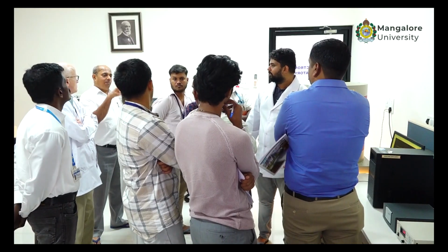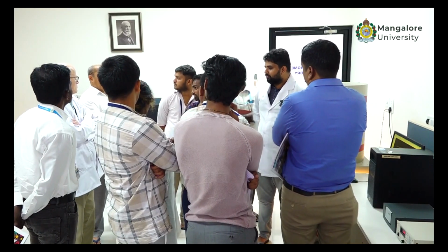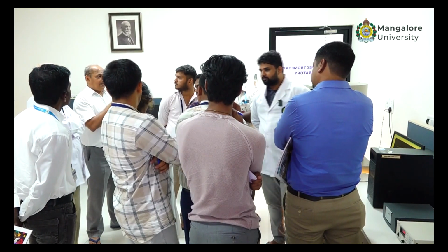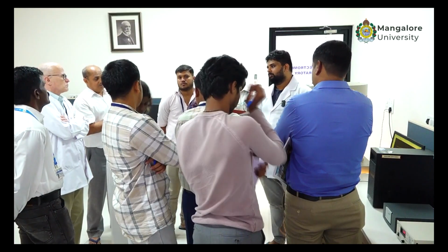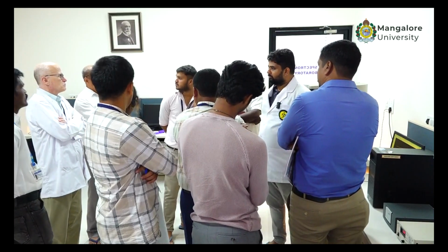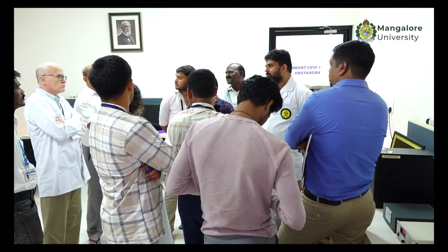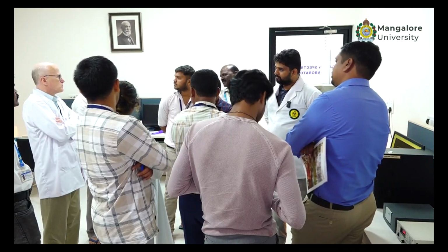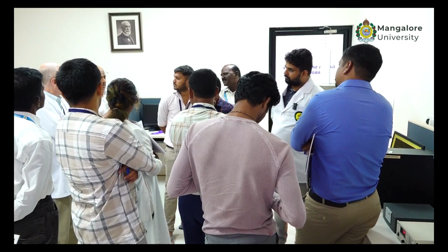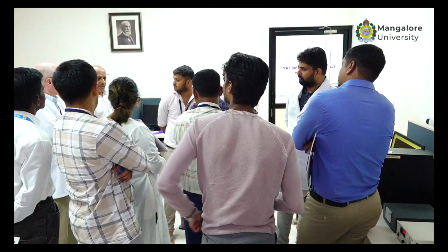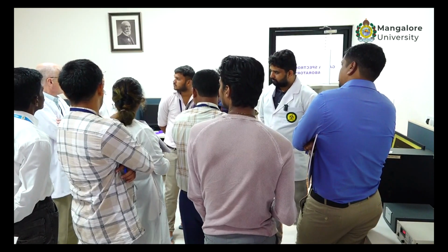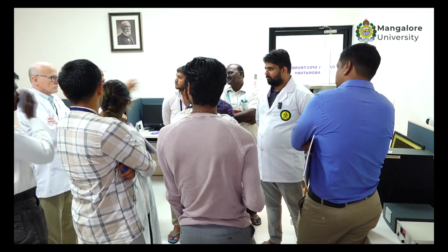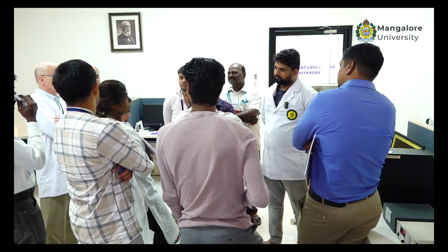High voltage is the operating voltage given to the detector. Each detector has a designed operating voltage. Once it is set, it is done. You are not going to change this daily. For example, if I switch on the detector today, I set the detector voltage at 4,500 volts today. That's it. You are not playing with that again. Then you are only collecting the data with the detector. You change the sample daily and acquire the spectrum. When it is switched off, we can do it again.